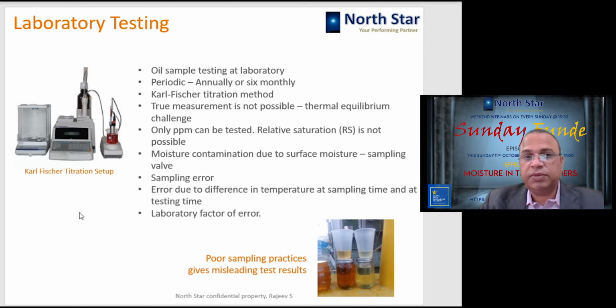Suppose, if you remember the graph which I showed, the blue colored cycles with a red mark, the sample after 6 or 7 months is taken in some other situation, and unfortunately at that time the equilibrium was such that more water has come from the solid insulation into the oil. Then, without any addition of moisture, the ppm will be shown high in the test sample. So from 5 ppm of the 6-month old value, suddenly you will find the ppm has gone to 20 ppm and you will panic. Oh, my transformer has a lot of moisture, but actually no water has gone inside the transformer. It is just because of thermal equilibrium that you are getting these confused results. So it is not a very true method giving you the correct picture.